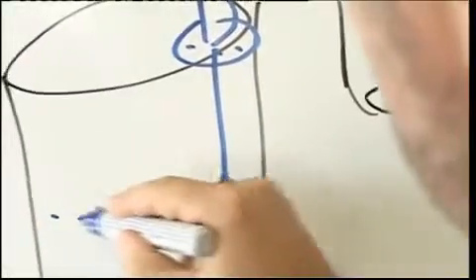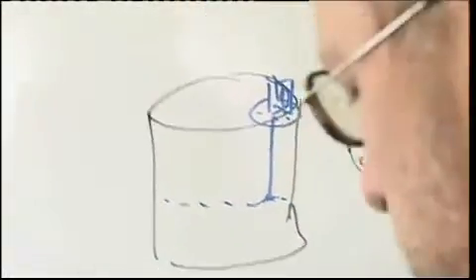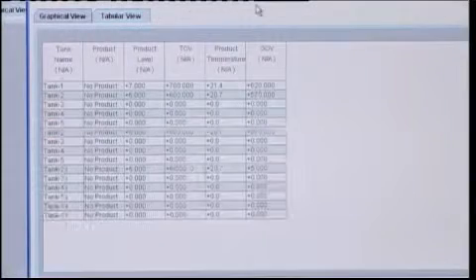Let's focus on the architecture of the Tank Vision concept. The Tank Vision tank scanner connects multiple tank gauges via one field loop and can handle a total of 15 tanks. Several gauge protocols are supported, of which Endress+Hauser Modbus and Sakura V1 are used most frequently. Optionally, the tank scanner can be equipped with a full set of tank inventory calculations.